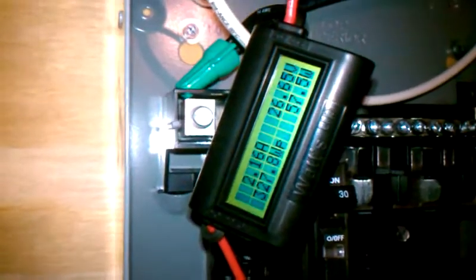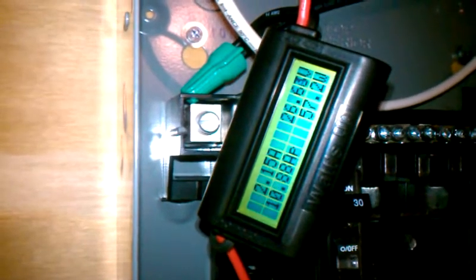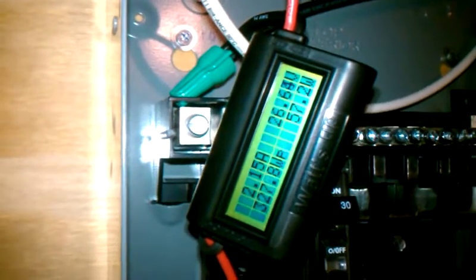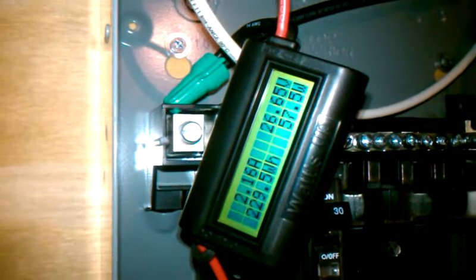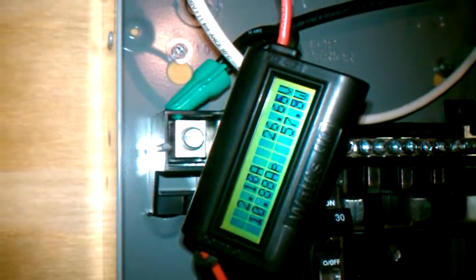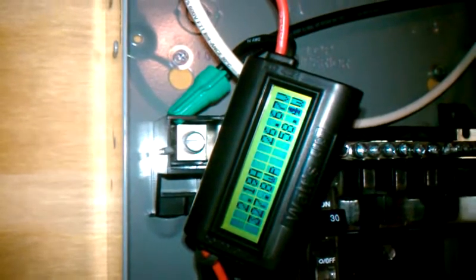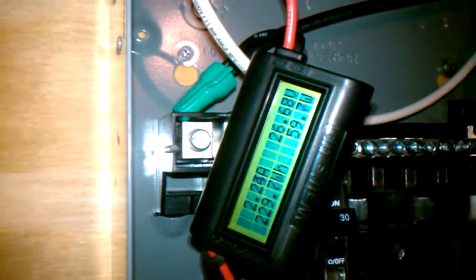I'm going to try and steady the camera so you can see this. 26.6 volts coming in. We're going to see if we can get one of these huge spikes. Right now there's a lot of clouds, but when the clouds move, this thing really jumps up. There's 10.88 amps max — 327 watts coming in off 350 watts of panels. It's not bad at all.